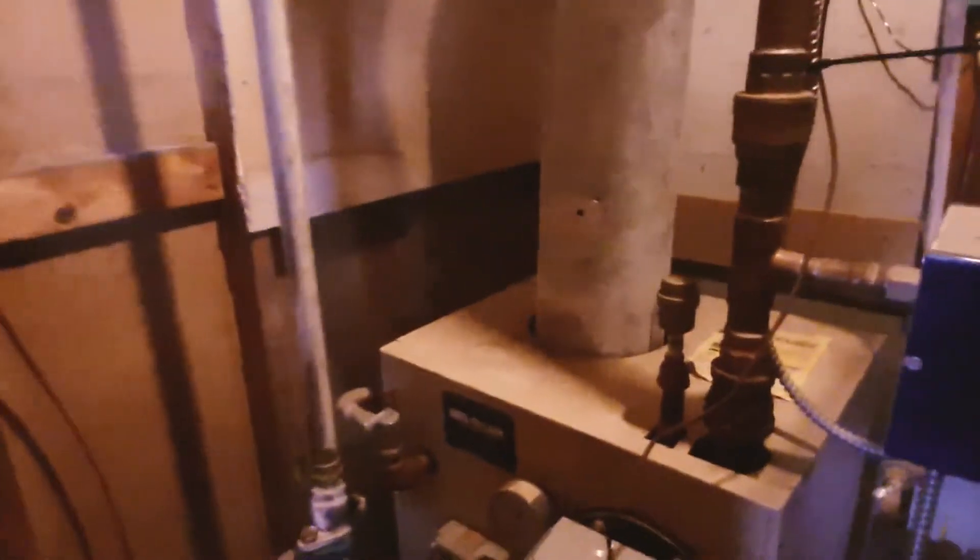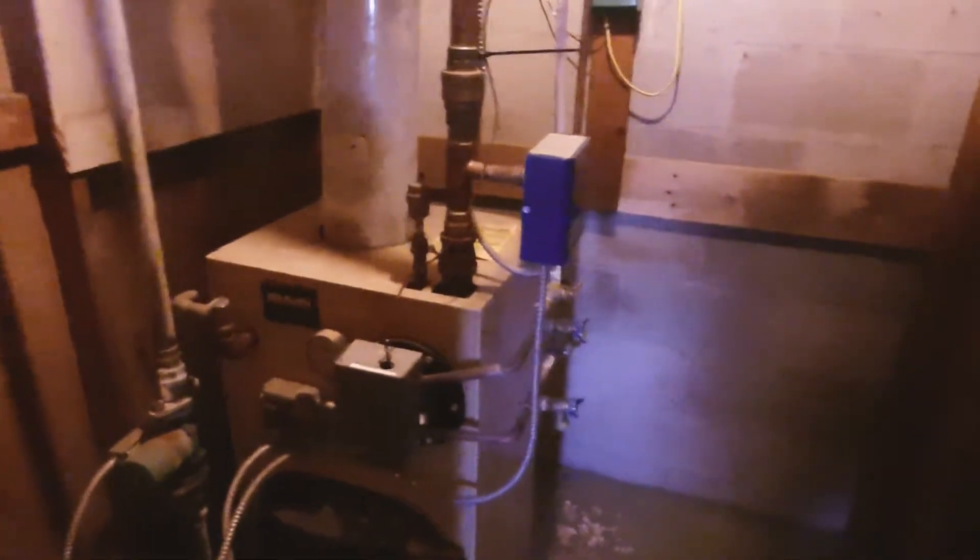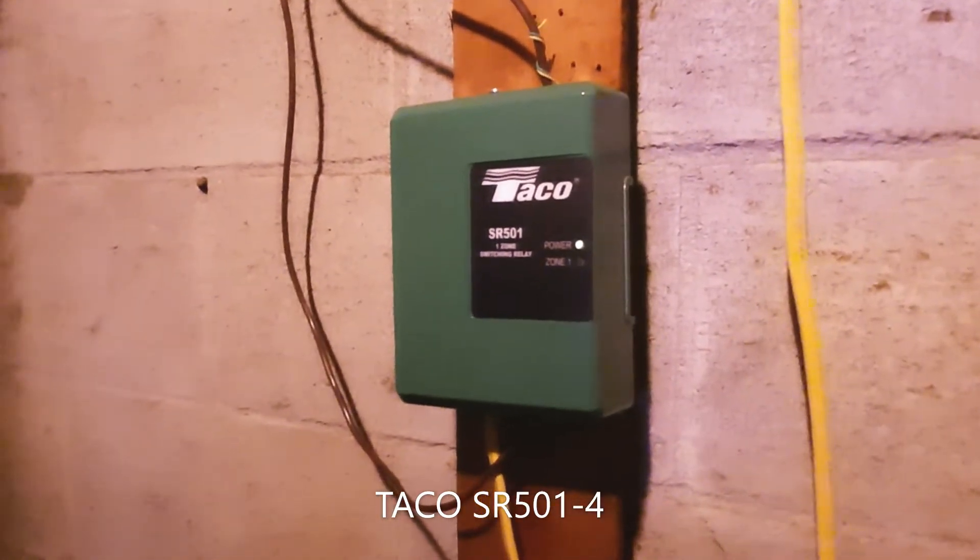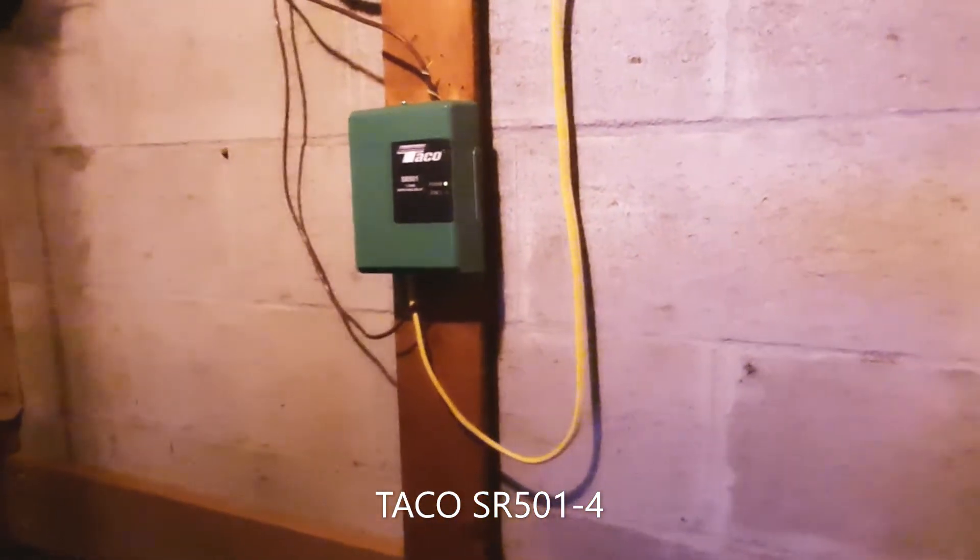The simple way of wiring this up so that it runs off a Nest, because you need a third common wire, is installing one of these Taco one-zone switching relays. It's an SR501. If you're going to do this yourself, you need to have a little bit of experience wiring electrical.